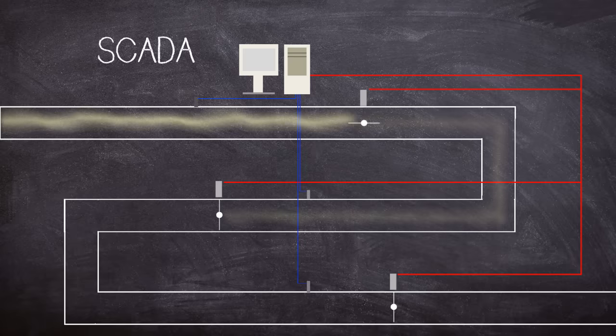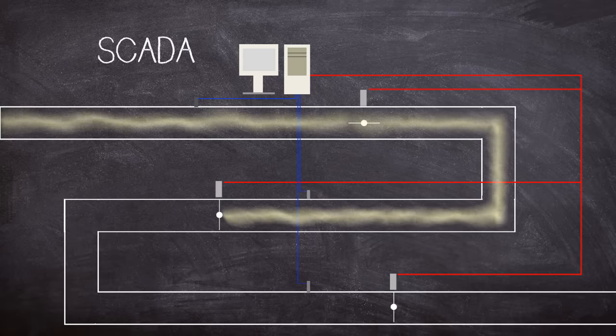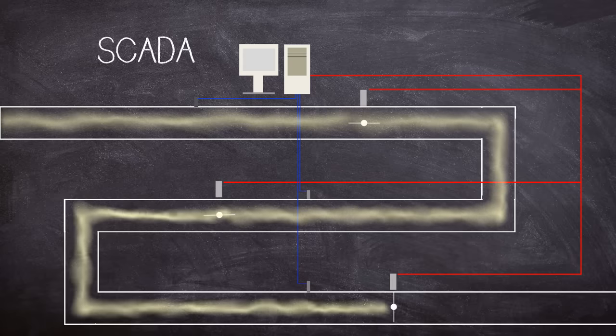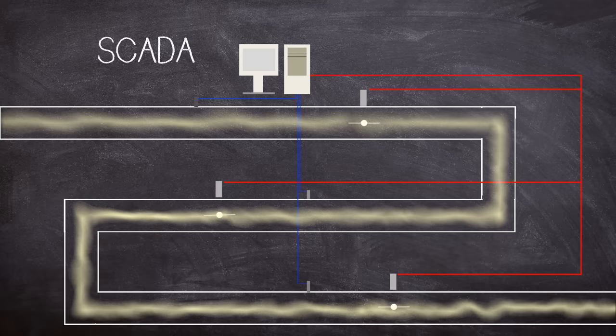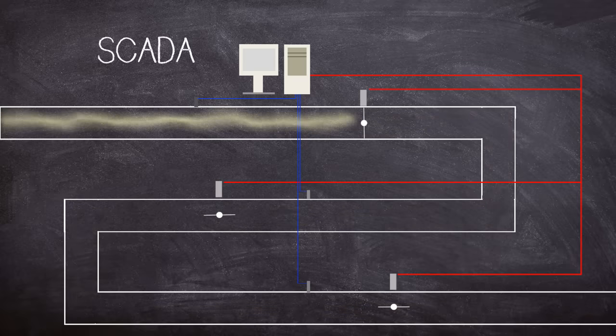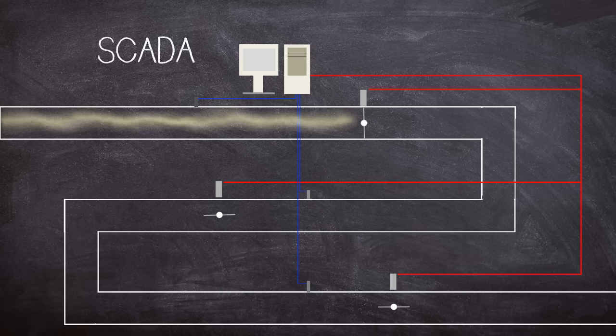The system consists of sensors, actuators, remote terminal units, a communications link, and the main SCADA computer. The SCADA shows a network on the computer screen to operators who can intervene to reduce pressures across the system by remotely operating valves. If situations developed that exceed preset values, an alarm can be given to the operators.